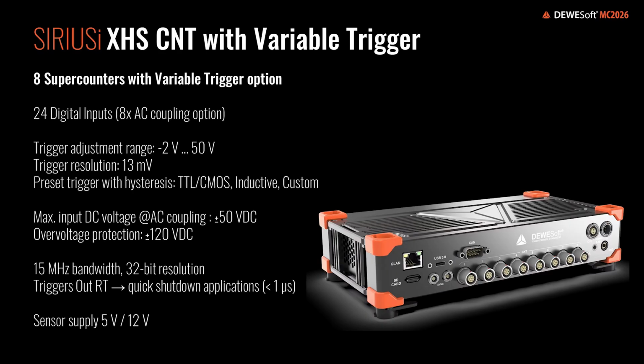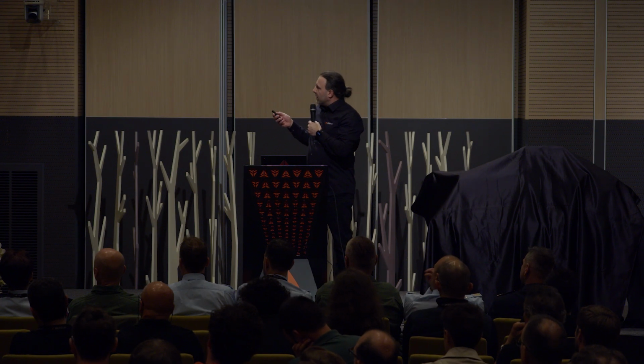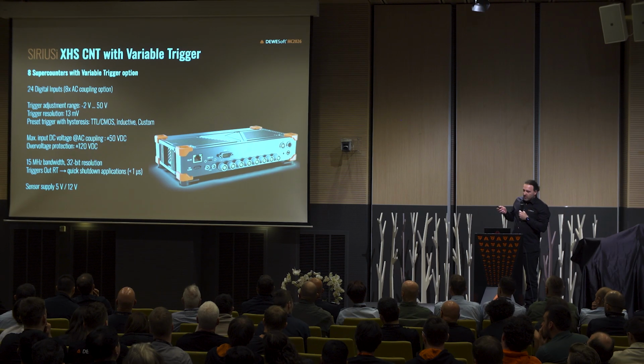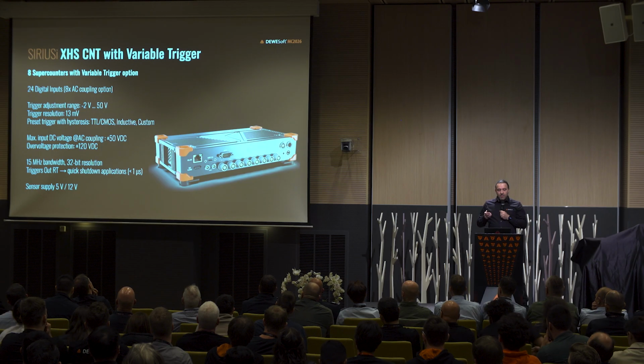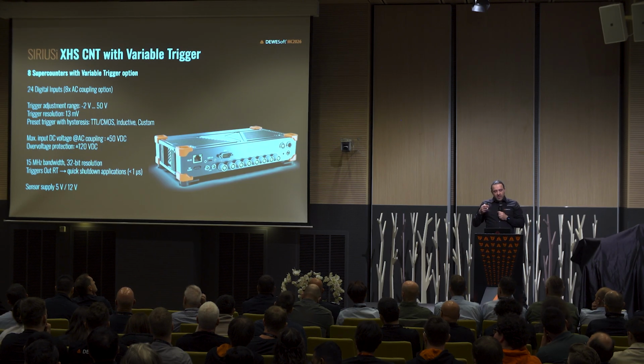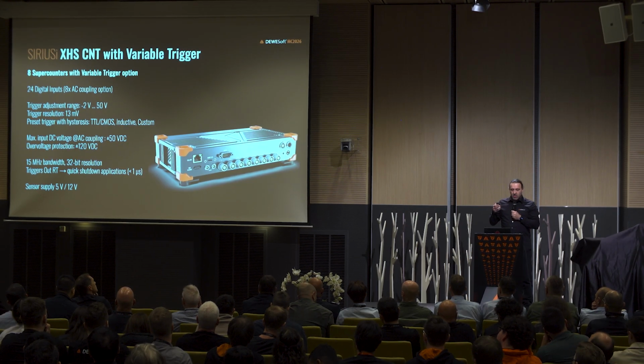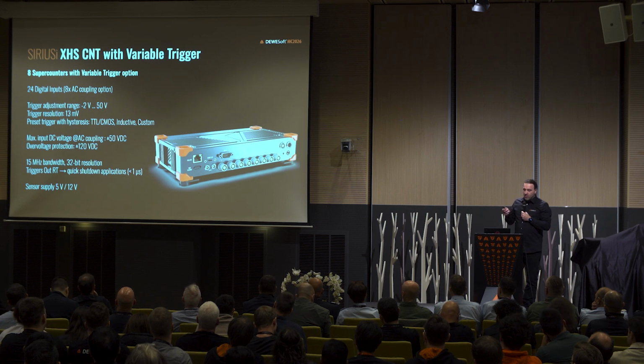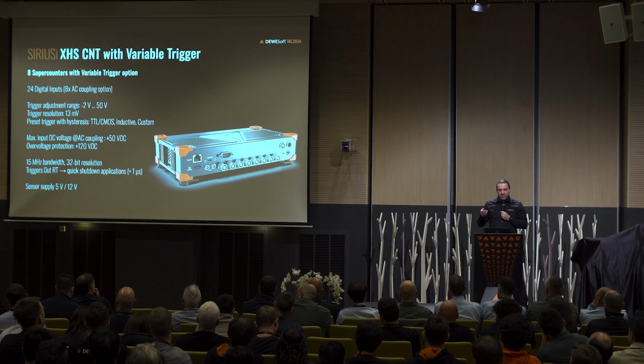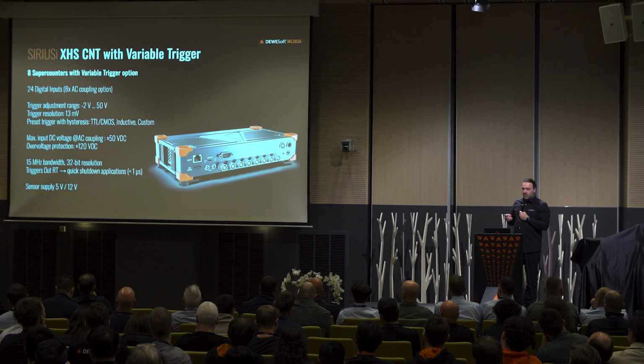As an add-on for XHS instruments, we designed a variable trigger counter module with 8 super counters. That means you have 24 digital inputs, and 8 of them can even be connected in AC coupling. Each digital input has 2 comparators where you can independently set any trigger voltage with custom hysteresis in a range of -2 to +50 volts.